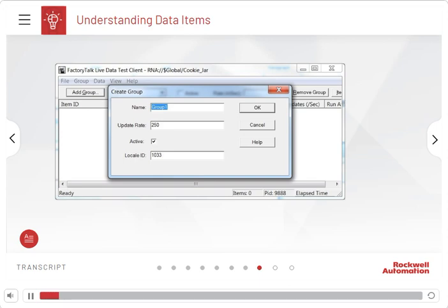Data items are created in a group from a single data server. You can create a group for a single data server, such as an RSLinx Classic topic, or various FactoryTalk View SE data servers. You cannot group data items together from an OPC server and a FactoryTalk server.